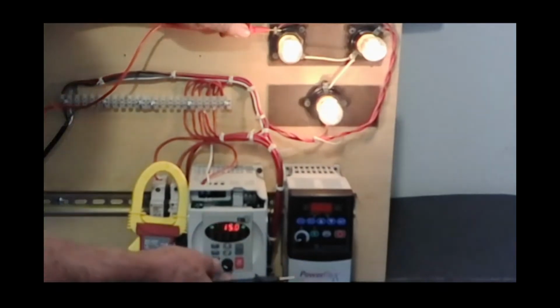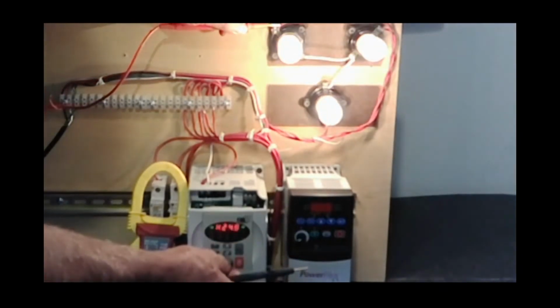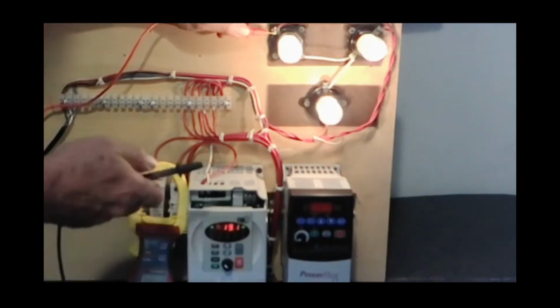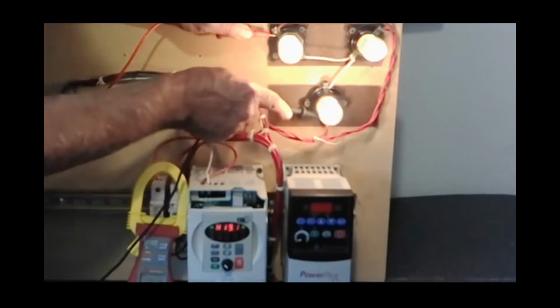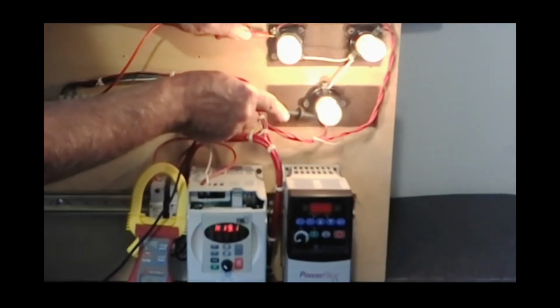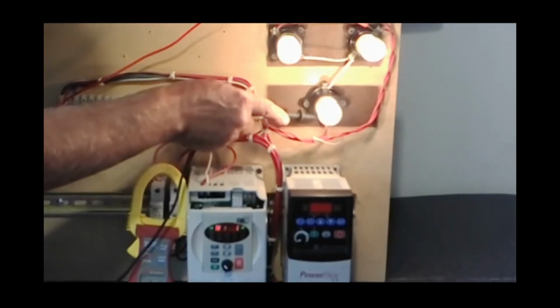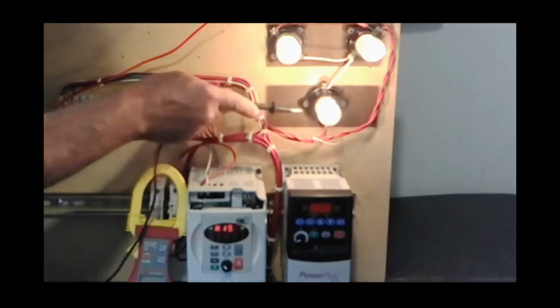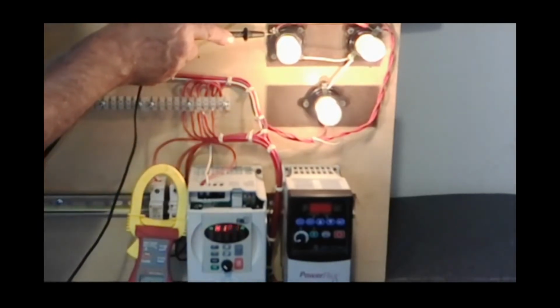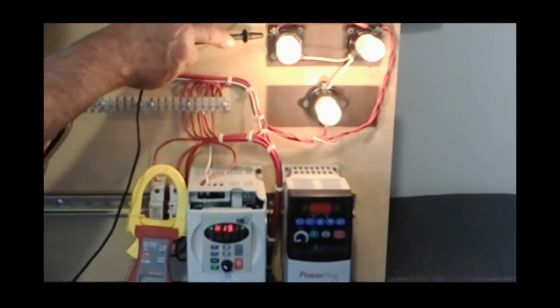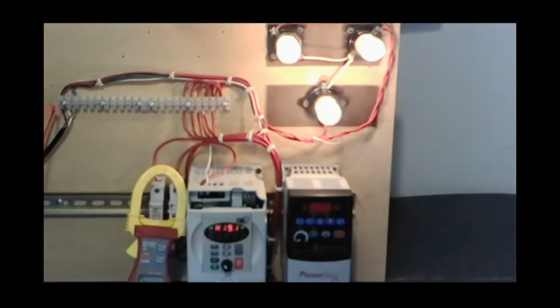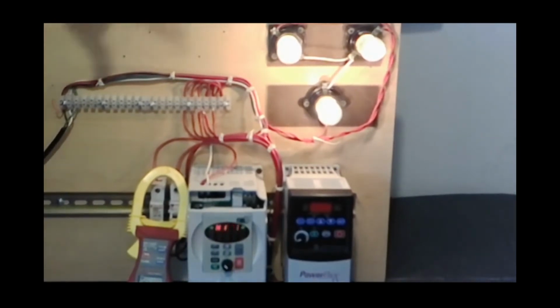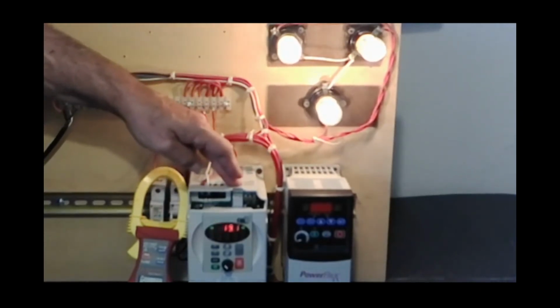If I measure right there at 15 hertz, let's go up to about 20 hertz so I don't get too bright and drown out the camera. If I measure from one phase to the next, I'm getting exactly 131.4 volts. If I measure from the other phase, I get 131.4 volts. If I measure to the next phase, again 131.3. So taking the readings right there across the load makes it very easy. I should have the same exact voltage across all three phases of the load. If I do not have all three phases identical in voltage, then there's a problem internally within the drive.